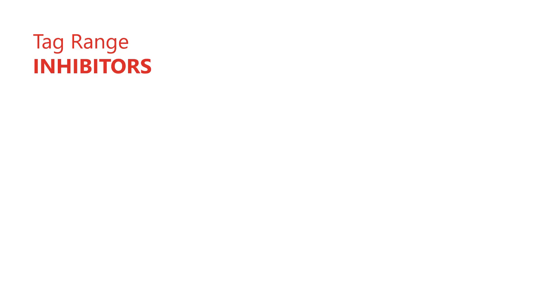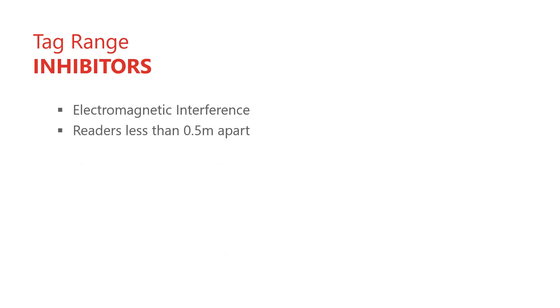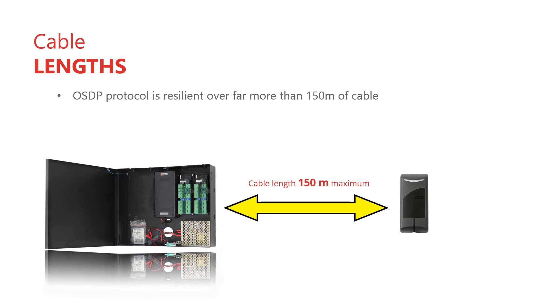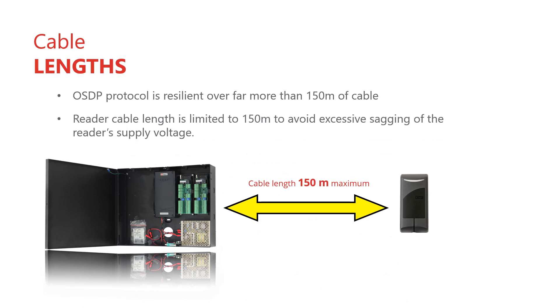Before we wire the reader cables, note that the reader-to-tag range can be impacted if there is strong electromagnetic interference, if readers are mounted closer than half a meter from each other, or if readers are mounted back to back on opposite sides of the same wall. Cut a length of two pair shielded cable long enough to comfortably route from the OSDP reader module to the reader location — no longer than 150 meters, as the reader's supply voltage will sag over longer lines.